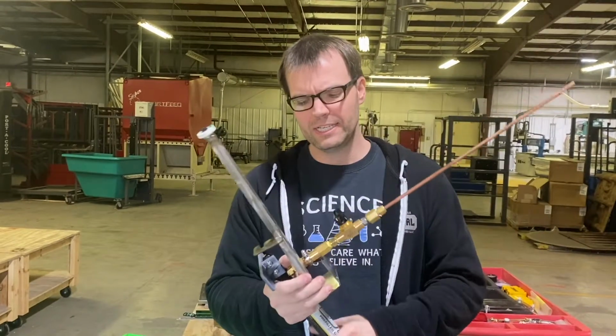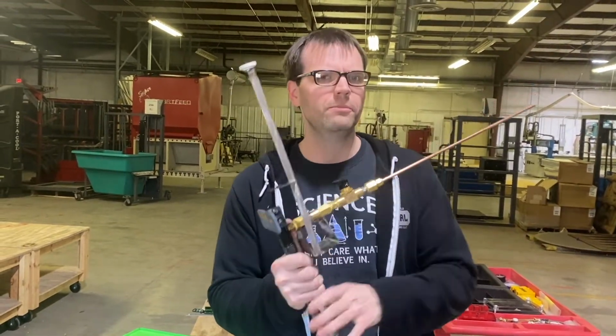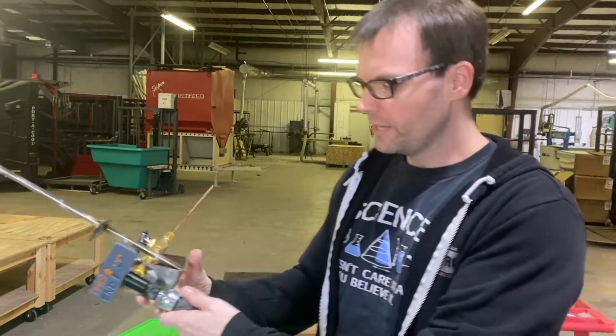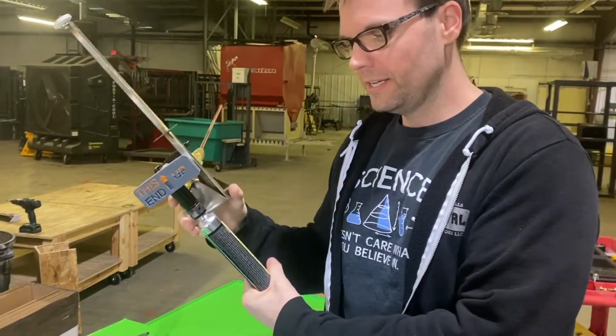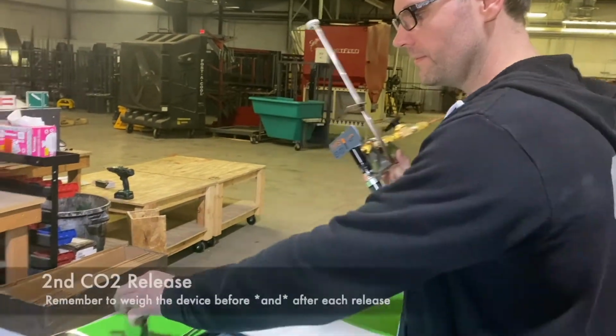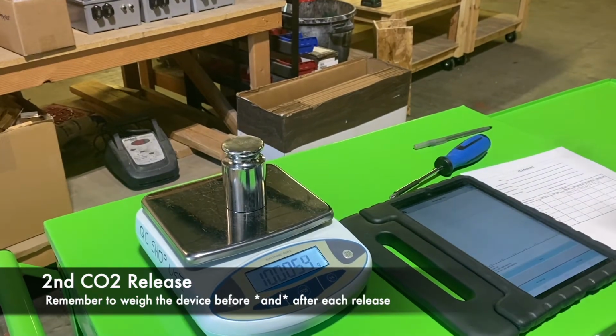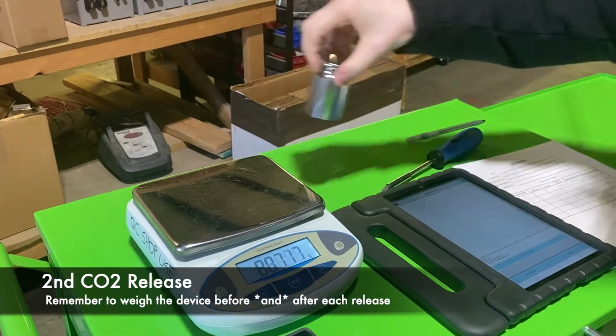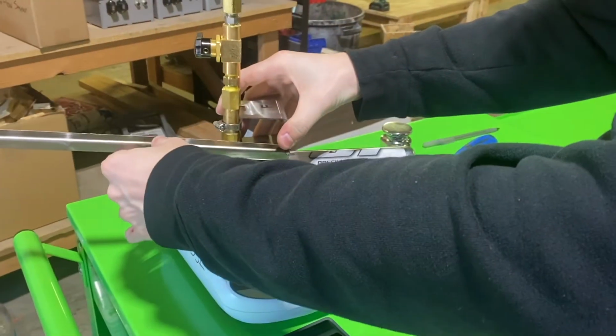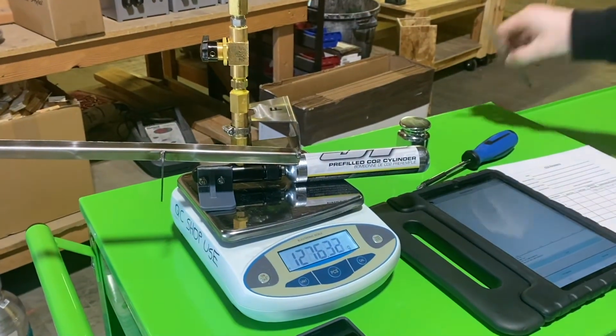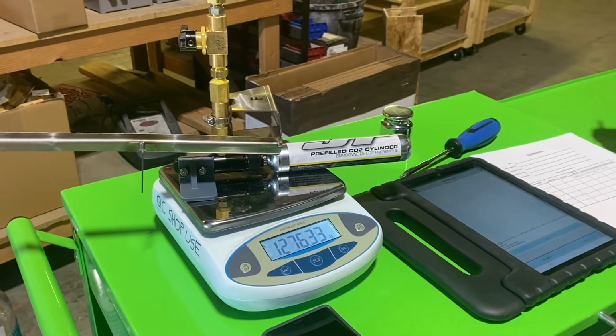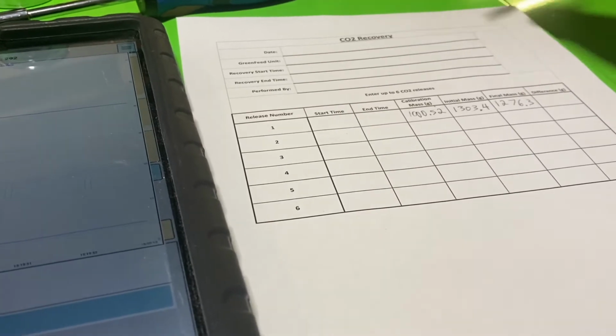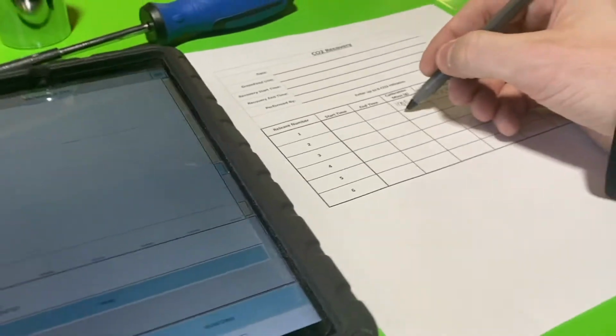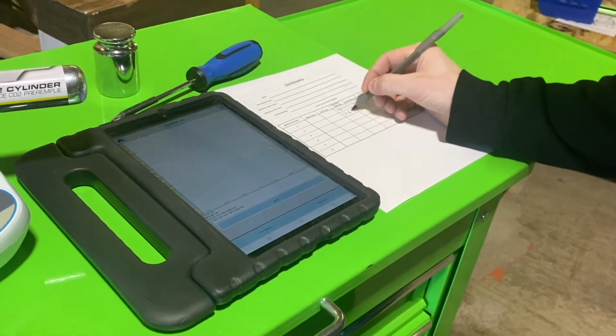Now we're ready for the next release, and I've warmed it up quite a bit. It's still cold, but I've warmed it up a bit. Again, we want to make sure there's no condensation or frost formed on it. We're going to zero our scale. We're going to use our calibration weight to make sure that it's reading 1000.5 grams. And then we're going to weigh our release device again. And it should be fairly close to what we measured on our final mass before. So now it's drifted a little bit, but not anything significant. 6.3.